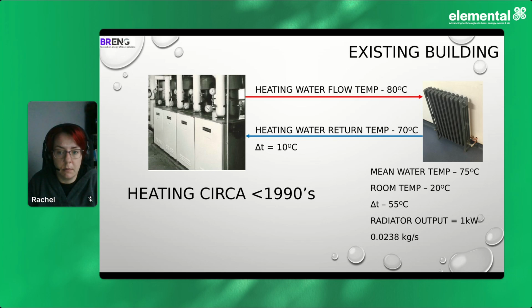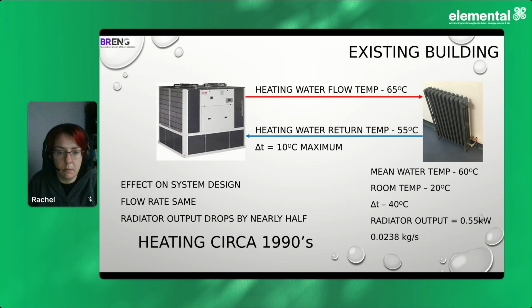This will give you an example. Pre-1990s, a heating system was designed on a flow and return temperature of 70/60, and that gave you a temperature difference between the radiator and the room. If you then come along and put an air to water heat pump on, now that heat pump, realistically, you can generate 65 degrees flow, get a 55-degree return, so it'll work at the same designed flow amount because it works on that temperature difference. But the radiator might not be big enough because it's not as hot.